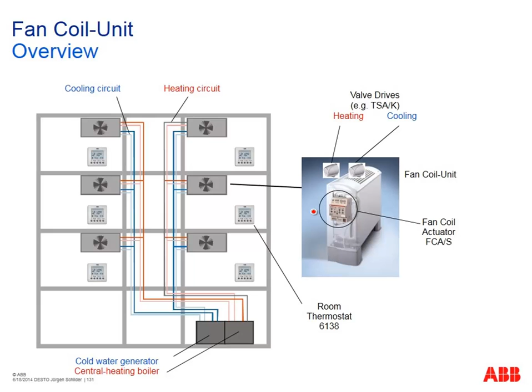On the next slide you can see what is inside such a fan coil unit. At first we have our 4 pipes: 2 pipes for the cold water, the incoming and the outgoing, and the same for our warm or hot water. Additionally we have our valve drive for heating and the valve drive for cooling, and all these valve drives and the fan are now controlled via our fan coil actuator FCA/S.